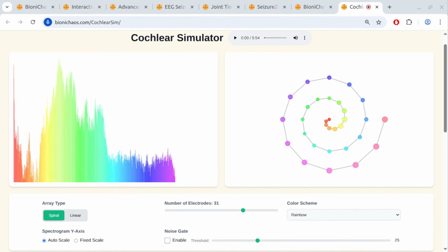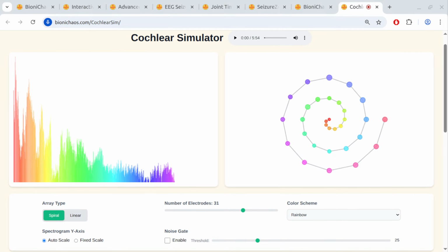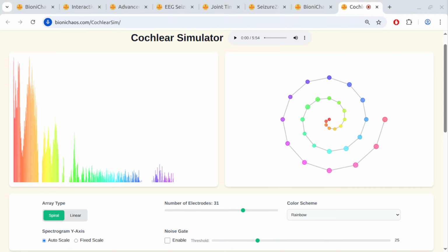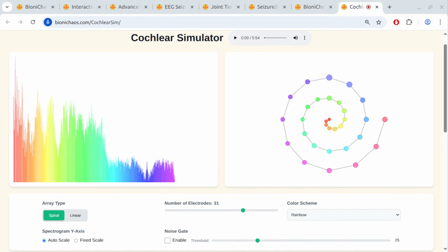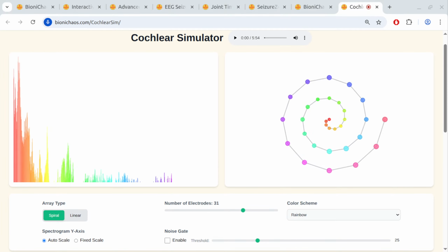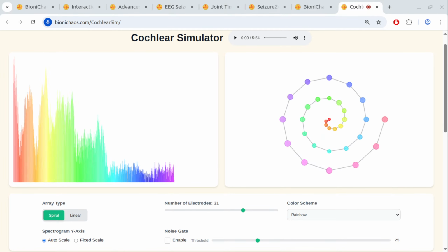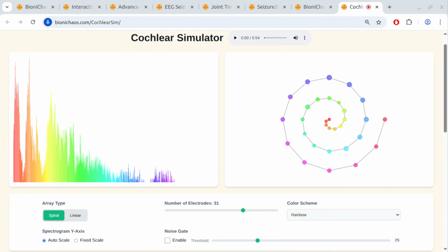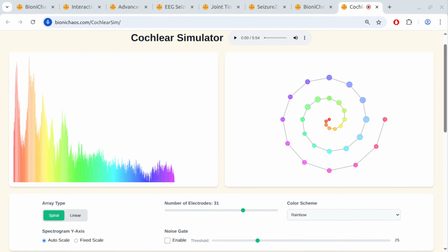And the innovation isn't just the outside stuff we see, right? The part that goes inside, the electrode array, that's seen big changes too. Oh, definitely. They're thinner now, which can mean shorter surgery, less discomfort. They're tougher too, more robust for everyday living. Okay, but here's where it gets really sci-fi. Current research is looking into designing these electrodes to slowly release drugs. Wow, drugs directly into the cochlea. Exactly. The idea is it could help stabilize cells that might be affected by the surgery itself, or maybe underlying conditions. It's this amazing potential blend of tech and biology.